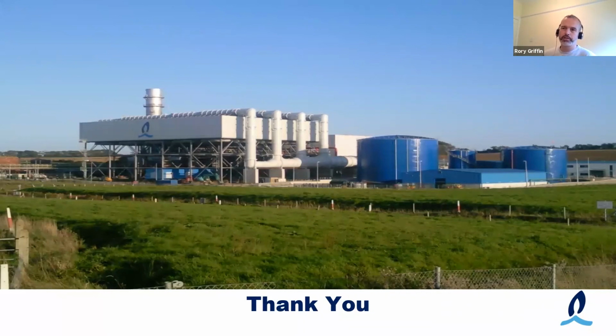During commissioning of a plant like Whitegate, it's expected to be able to trip to island mode. So what that means is, let's say the 220 kV breaker opened on the transformer, the unit should be able to drop back and just feed its own auxiliary supplies, so maybe 4 or 5 megawatts. And it should be able to hold that position until the grid instruct to maybe resynchronize across the 220 kV breaker. So that's one scenario, and the unit was tested during the commissioning phase.